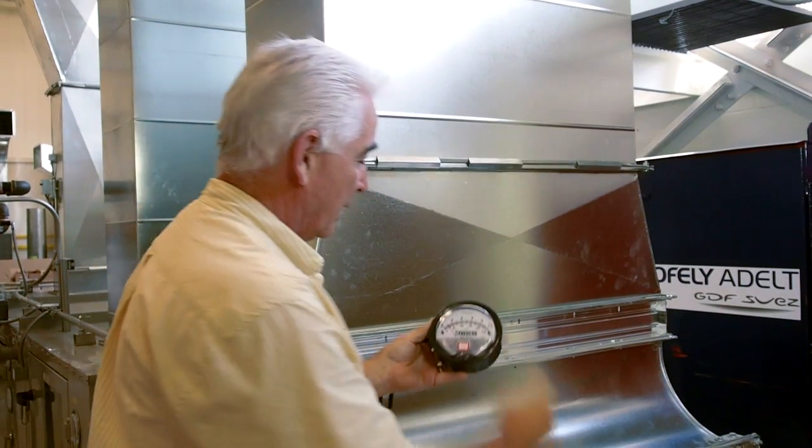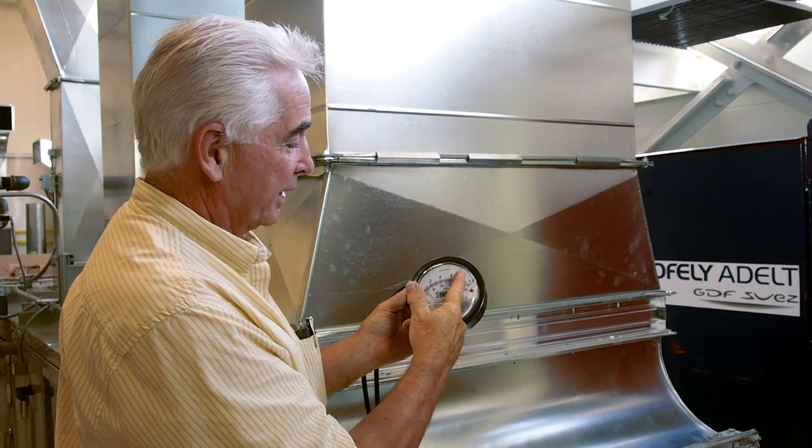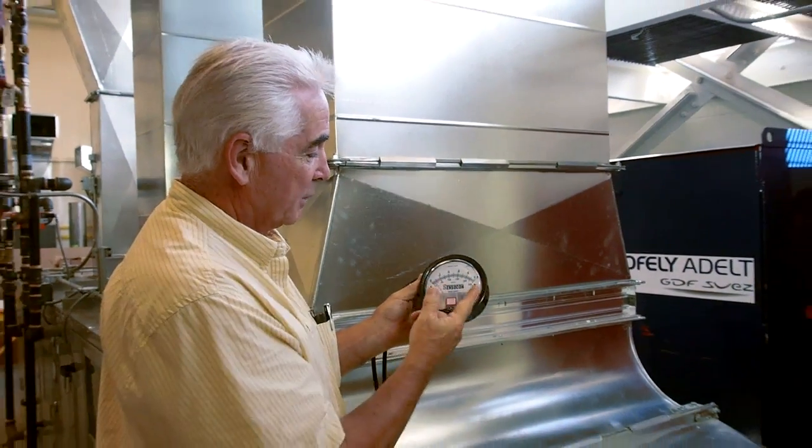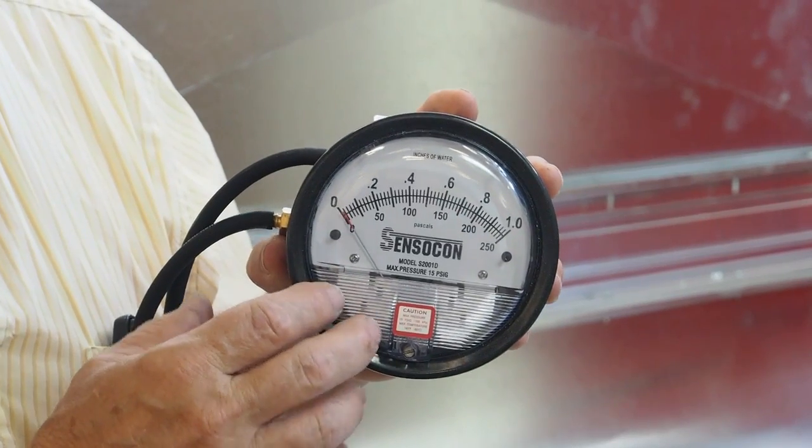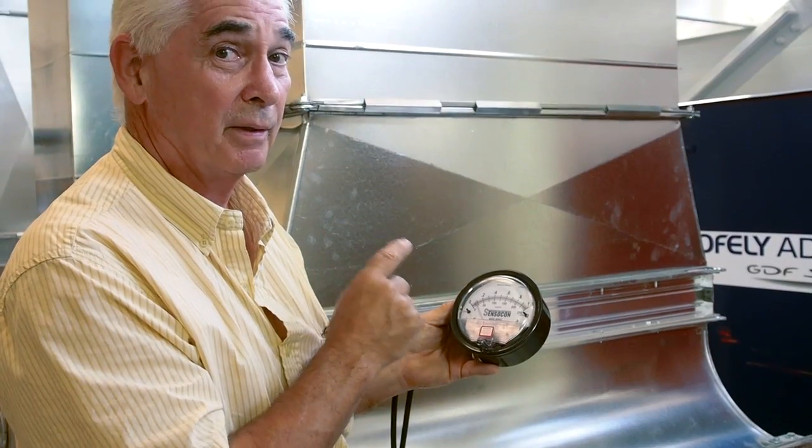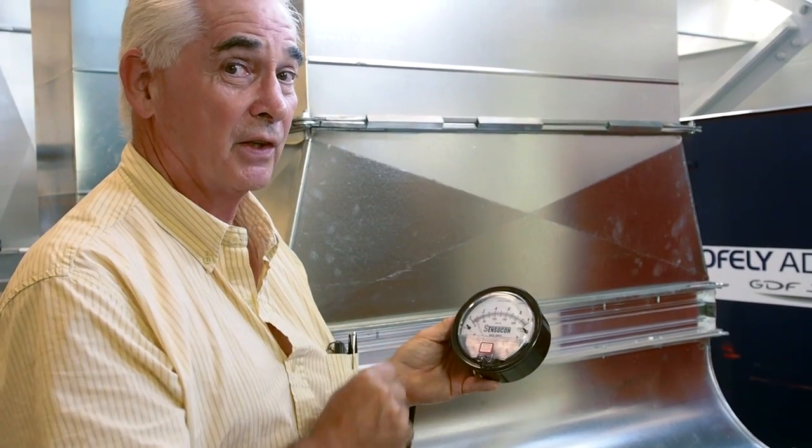And we hook the static to the bottom port. The top port is going to push the arrow this way. The bottom port is going to push it this way. So we're going to be left with a reading in velocity pressure. Total pressure minus static pressure is velocity pressure.